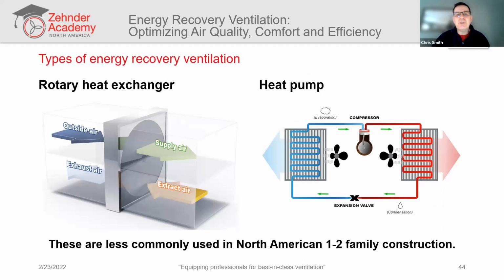So there are different methods of doing this. Just to very briefly look at a couple of methods that are commonly used, but not common in residential settings in North America, at least not in 1 and 2 family. You might see these more in multifamily situations, but one is a rotary heat exchanger or an enthalpy wheel. You commonly hear of an enthalpy wheel or a heat exchange wheel. And this basically has the supply air duct and the extract air duct located right next to each other, where you have a wheel that is located in between those two ducts.